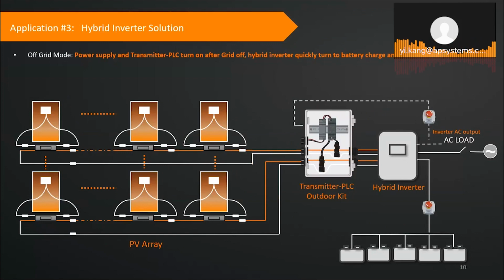bank or storage, they want the PV system to continue operating when the grid is off, right? That's common sense. It's a reasonable request. When that is requested by your customer, you have to change the wiring to connect directly to the hybrid inverter AC load side. So when the grid is off, normally the hybrid inverter will have a function, quickly in milliseconds, switching from grid supporting to battery supporting. And they keep the AC load supported all the time.